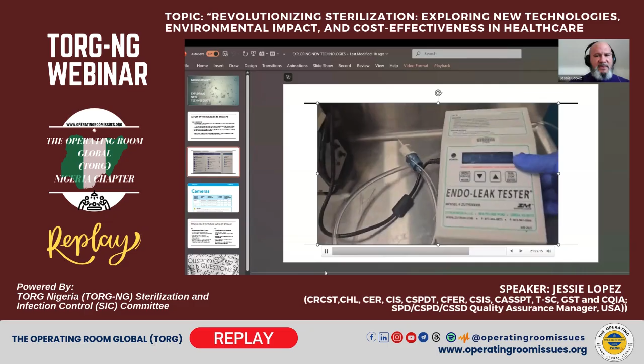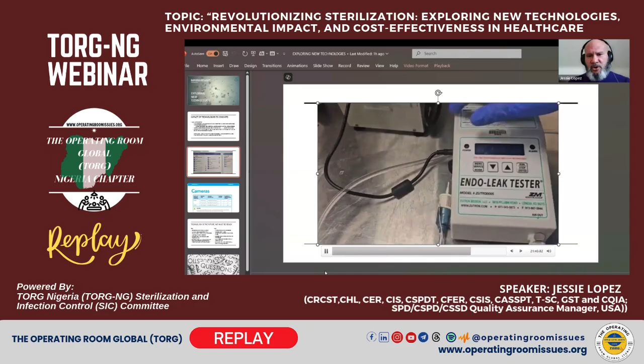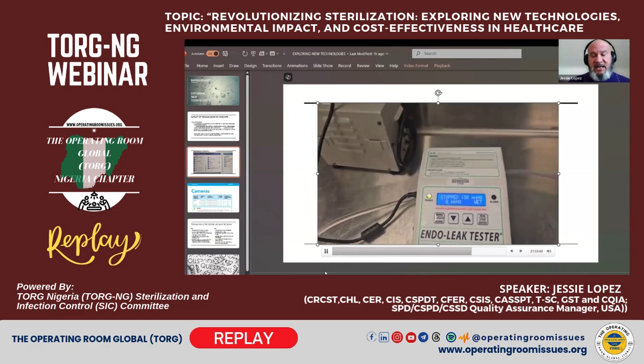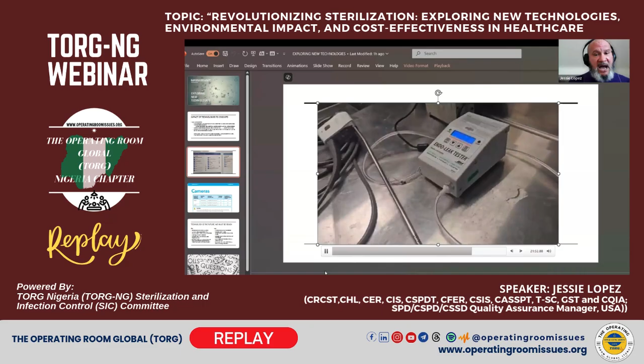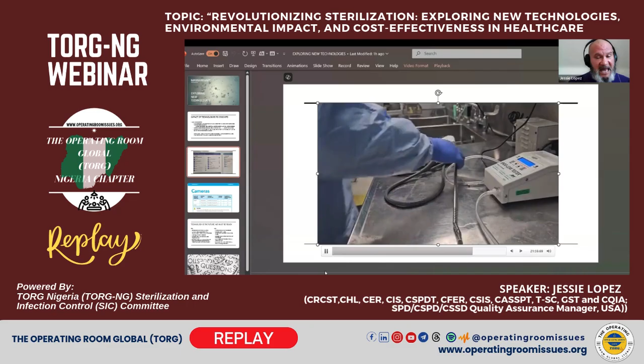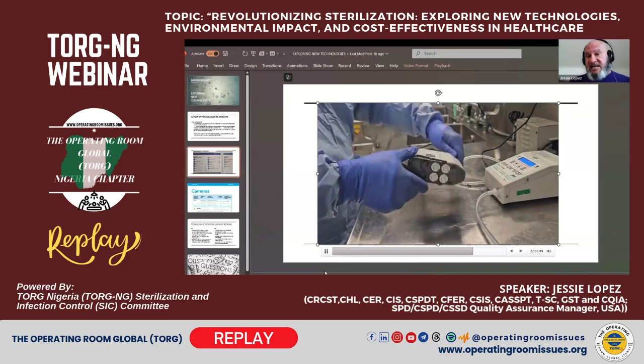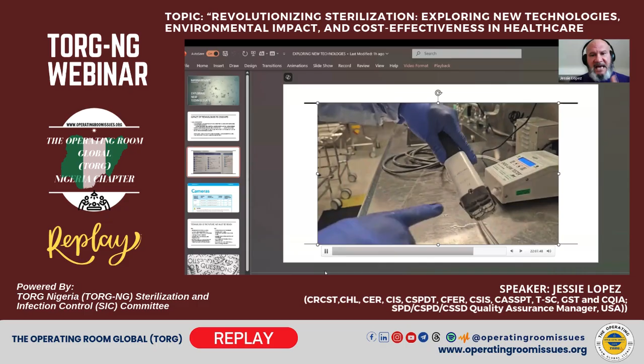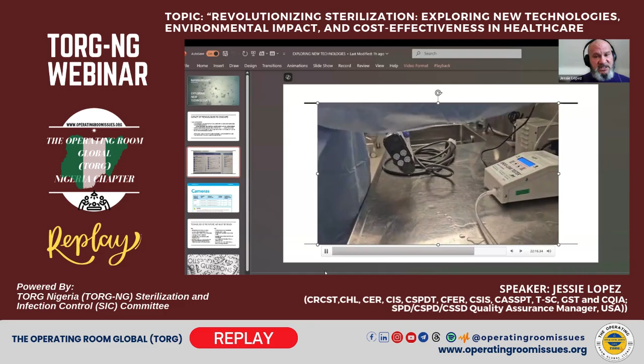This part of the IFU requires leak testing. Okay, leak testing is done at this point because of the aggressive cleaning techniques that we utilize; pressurized water can possibly damage the internal lumens. Those internal lumens are coated with a rubber, a Teflon coating that can be damaged if we utilize too high of a pressure of water. The ultrasonic cleaner is actually an aggressive cleaner. Okay, it's not really suitable for plastic, rubbers, glass, wood, cork, and this component has all that: plastic, rubber, the glass distal tip. Okay, so the leak testing is designed to see, okay, it's validated to be cleaned with an ultrasonic cleaner, but let's just check this device to make sure that it's going to hold up its integrity.